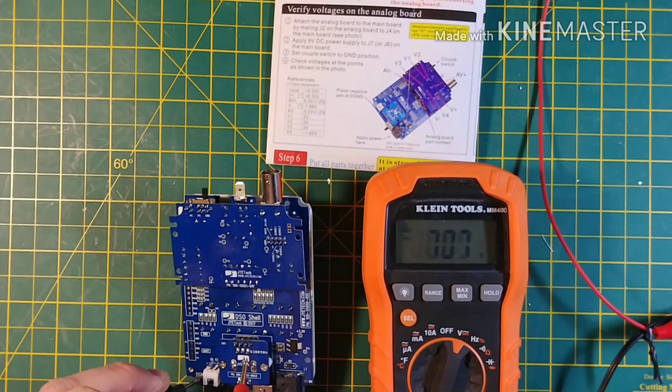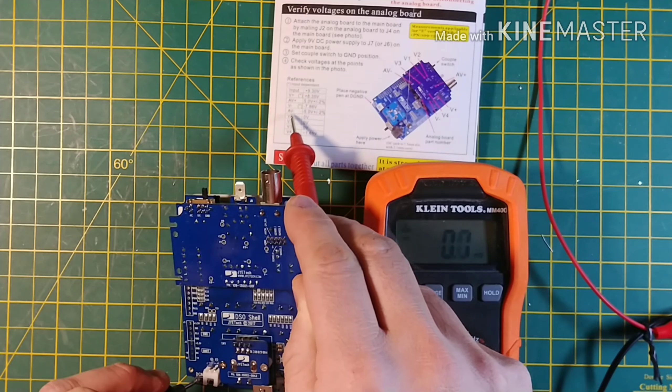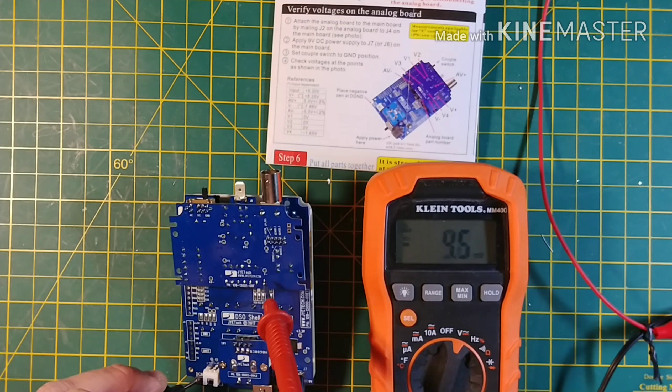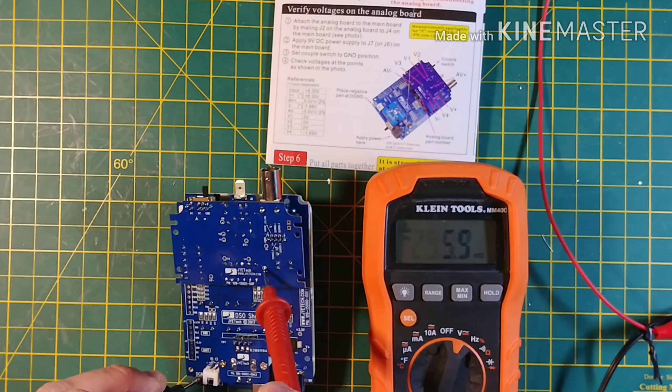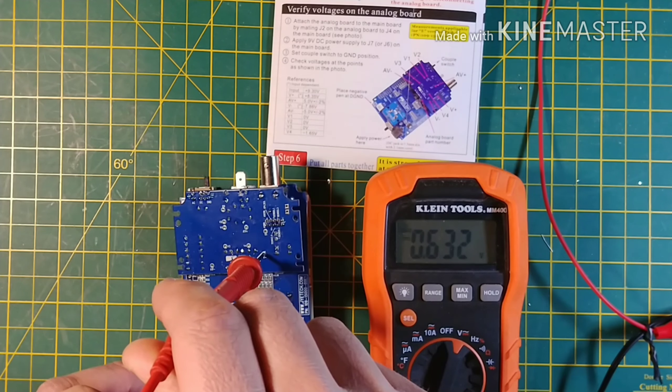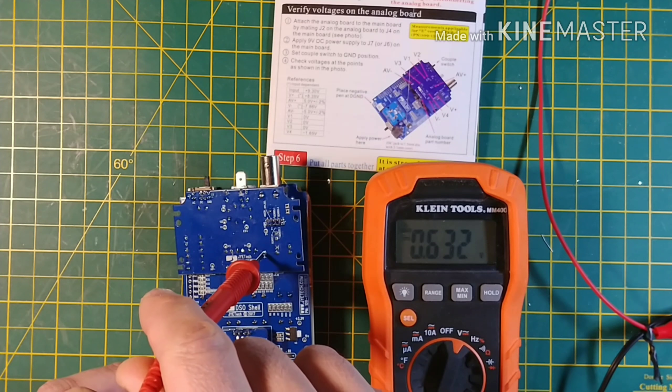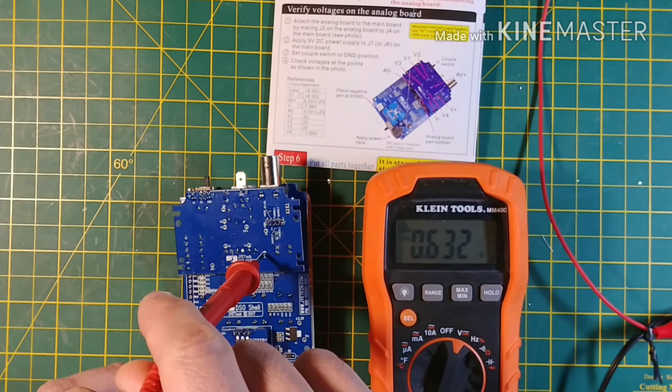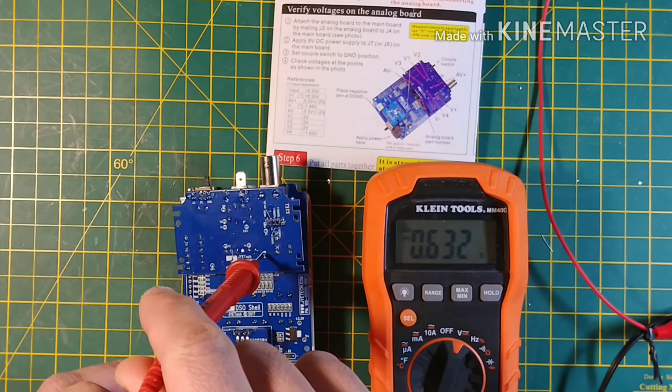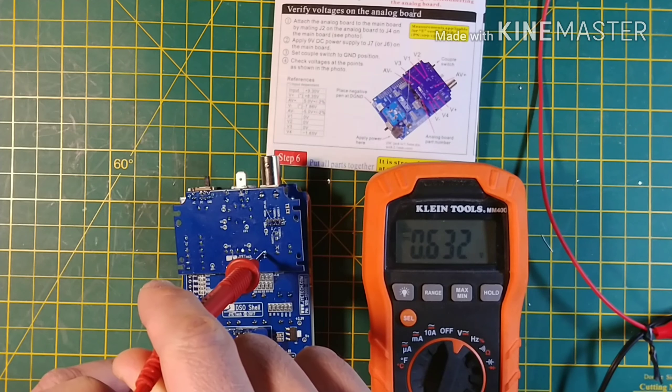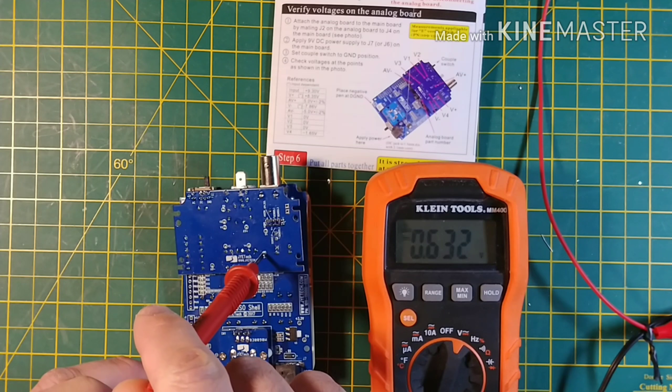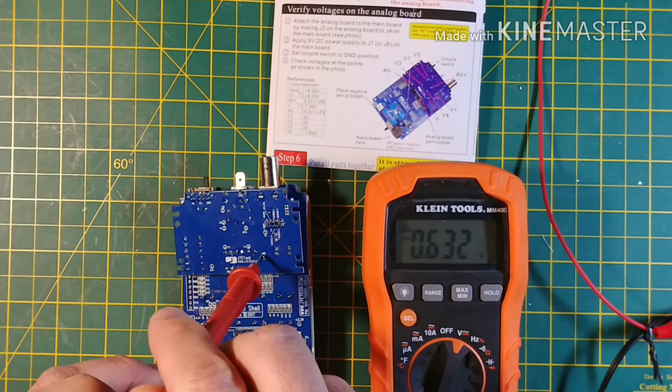The next voltage check is V-minus. Which is located right here. We are supposed to see minus 7.86 volts and we see 0.632. That is incorrect.